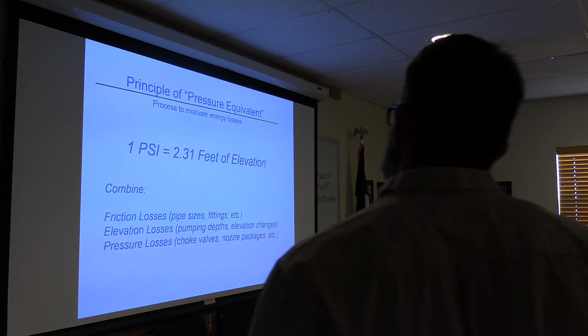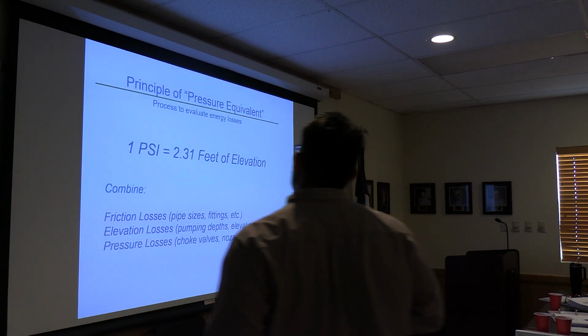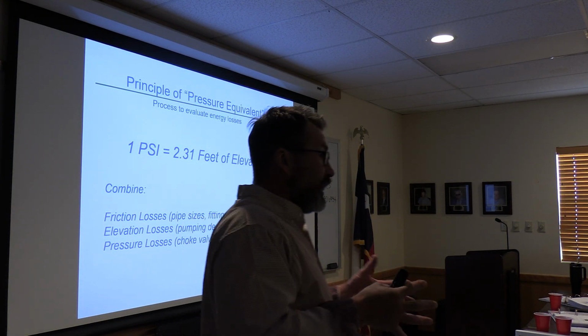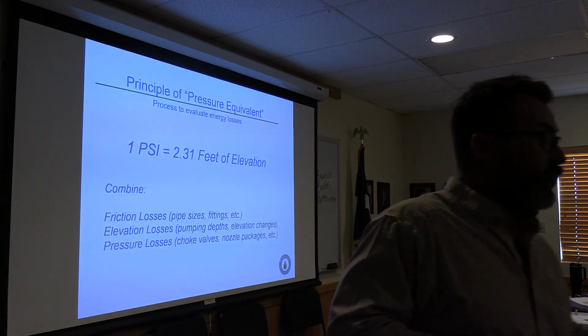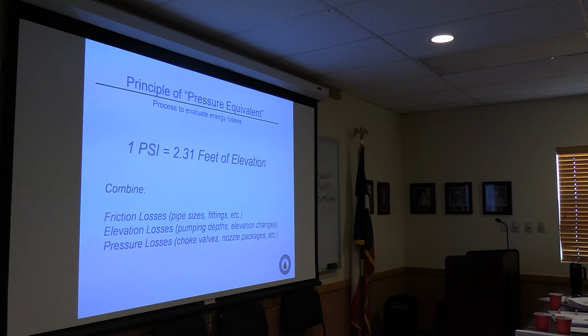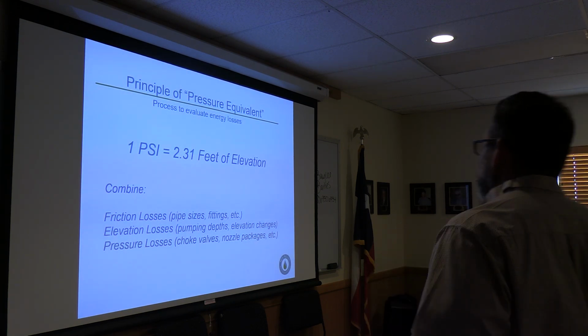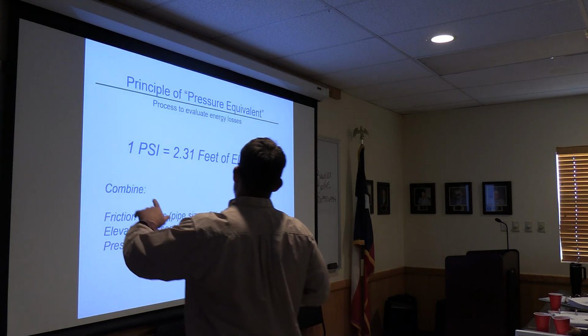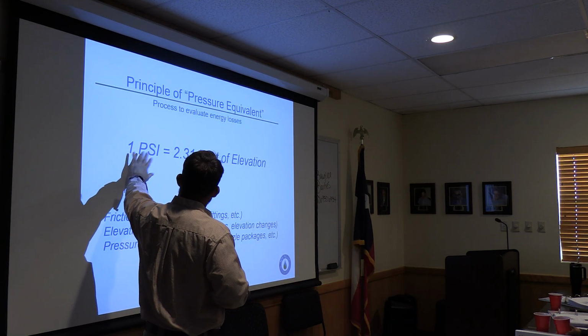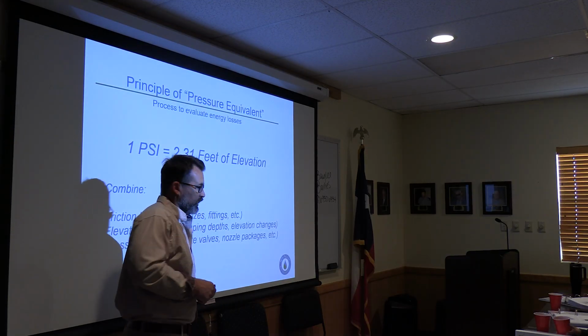You remember earlier I mentioned I want to get to common denominators. I want to get to a common language. And we talked about dollars. The quicker I can get to dollars, the more everything can talk to each other. In these systems, the pressure equivalent is the equivalent of that. So the thought to burn in your mind: 1 psi is 2.31 feet of elevation.